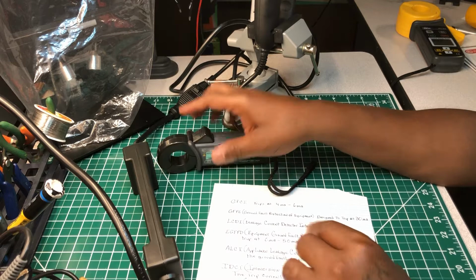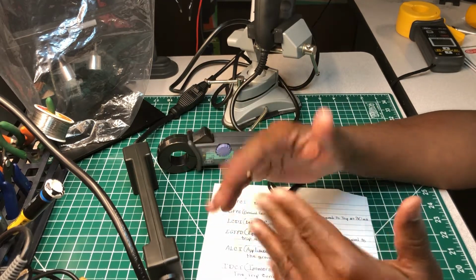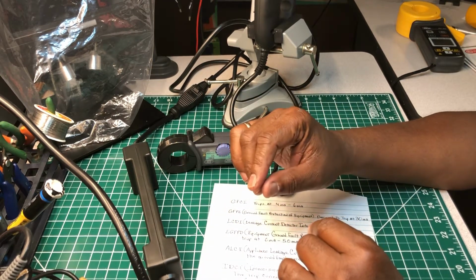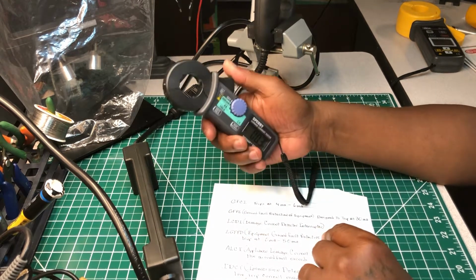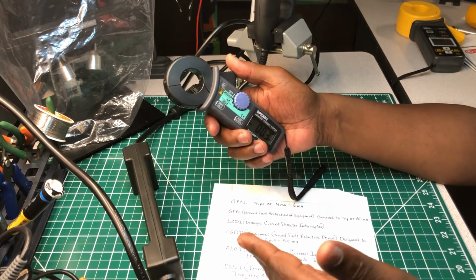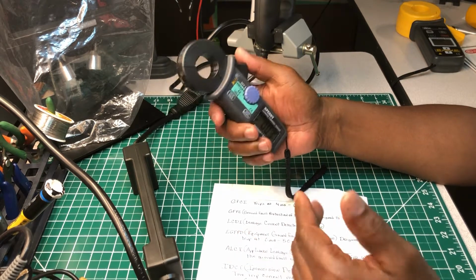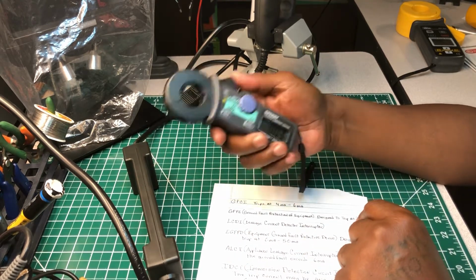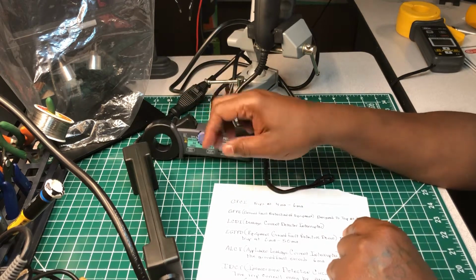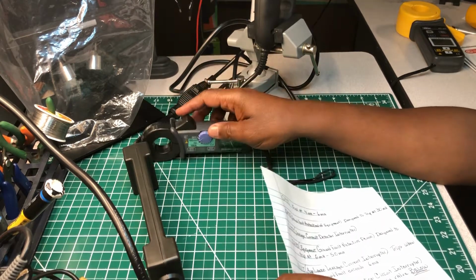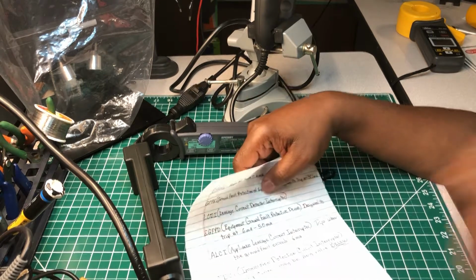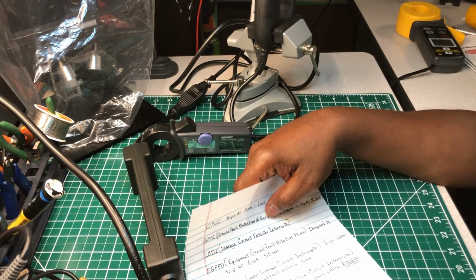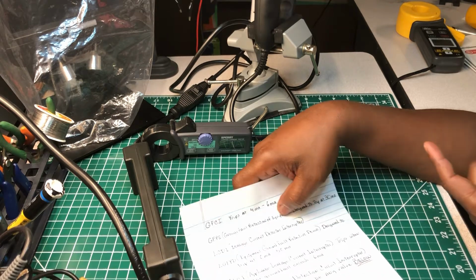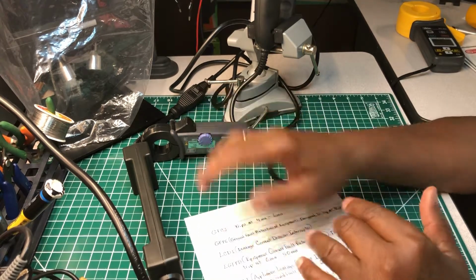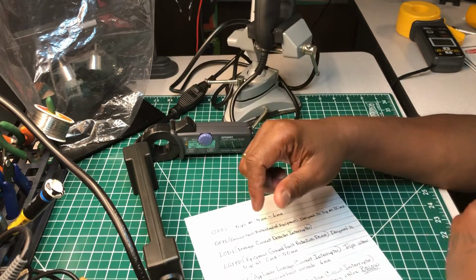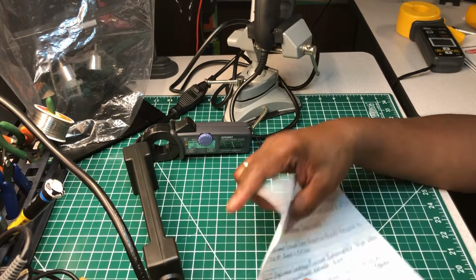If you're working on three-phase and it didn't have a neutral, you just wrap this around all three phases and see what's leaking. If it had a neutral, you put the neutral in with the three phases, and you take a reading to see which was tripping, and why it's tripping. Milliamp testing is very important, and like I said, I'll get to that in a minute because I do have some literature over here I want to show you guys. So if you're interested in buying one, you may say, well, I don't know how to use it. That's why I'm going to show you what I have over here to help you out.